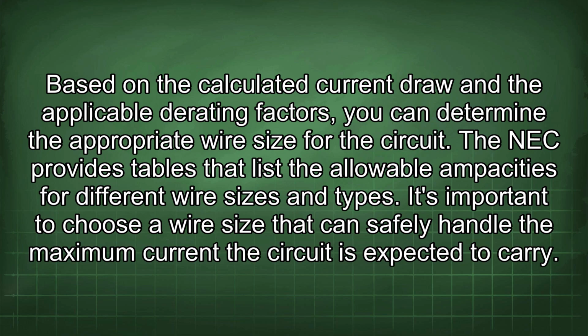Based on the calculated current draw and the applicable derating factors, you can determine the appropriate wire size for the circuit. The NEC provides tables that list the allowable ampacities for different wire sizes and types. It's important to choose a wire size that can safely handle the maximum current a circuit is expected to carry.